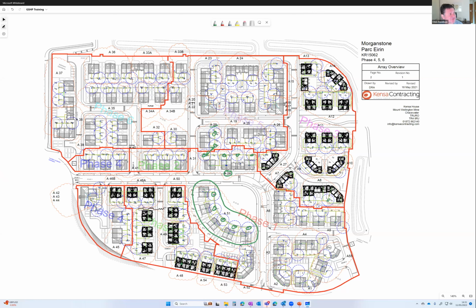If we've got a heating only system like this, we would see interference between the boreholes, even at 20 meters separation. When you're below 16 meters, it starts to ramp up. And if you were to do something like this on 6 meter spacings, you'd have an awful job getting a sustainable ground loop out of it.